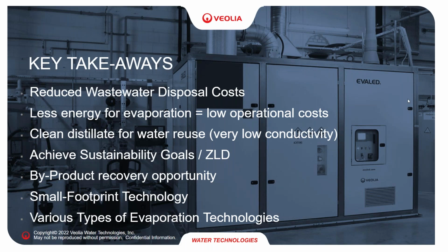In most applications, just about all of them, the distillate is available for water reuse. It's not going to be as necessarily as good as DI water, but in a lot of applications it is close, and it could be potentially polished a little bit if it needs to be a little bit higher quality. But typically it's as good as RO water quality as that you would have in your application.